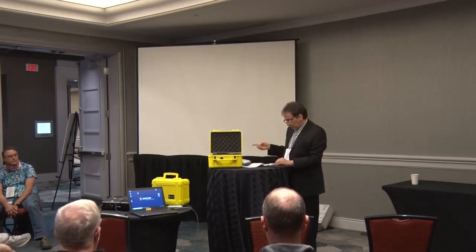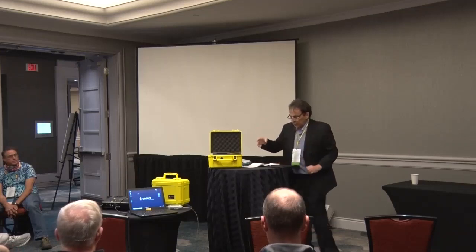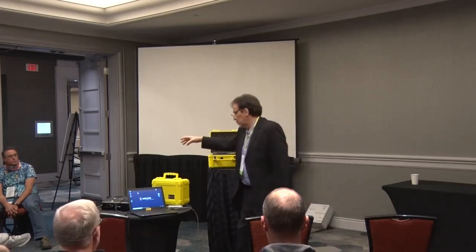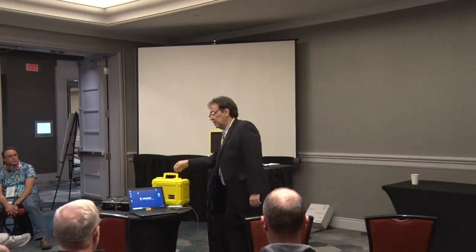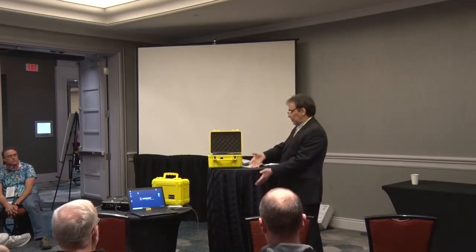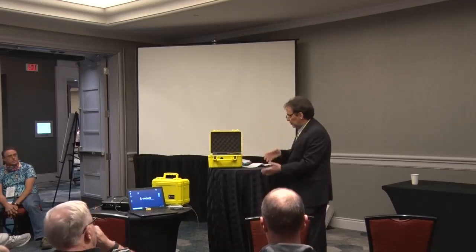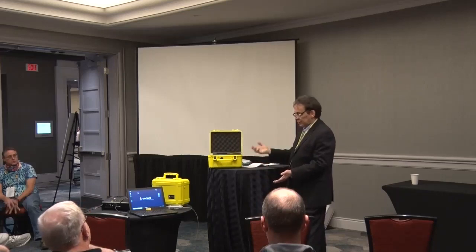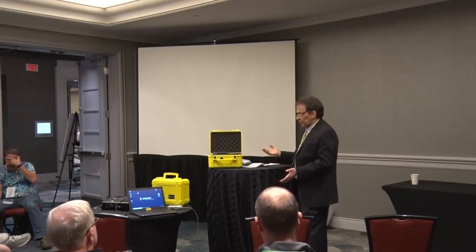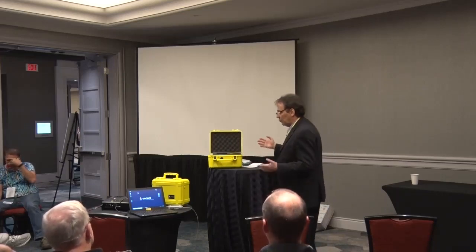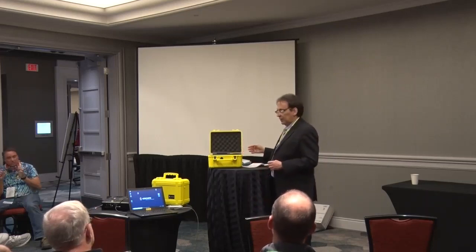So, yeah, Matt mentioned before that just because this is reading a high concentration doesn't necessarily mean you have a huge source coming out, right? Your source term coming out is the concentration times the airflow. So keep that in mind when you're interpreting your readings.